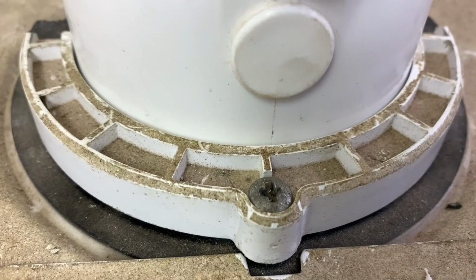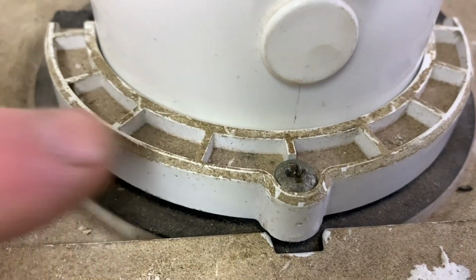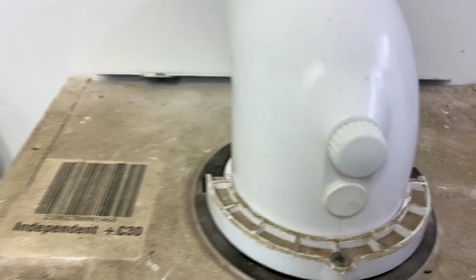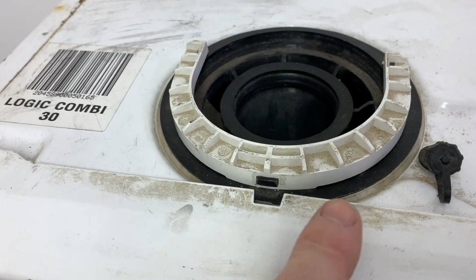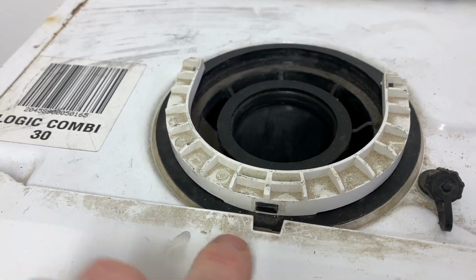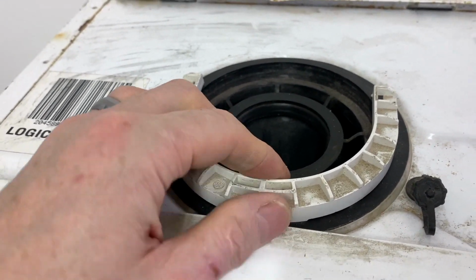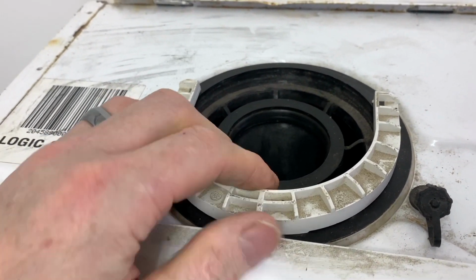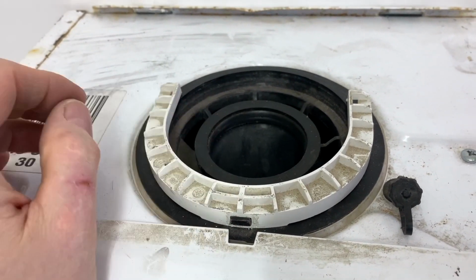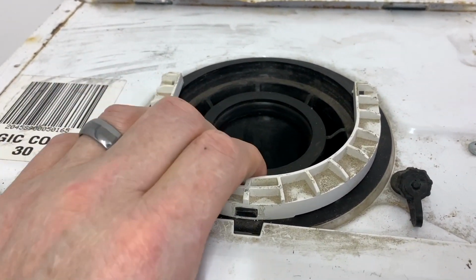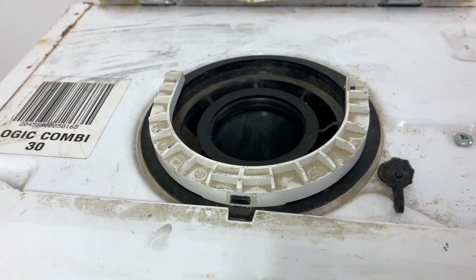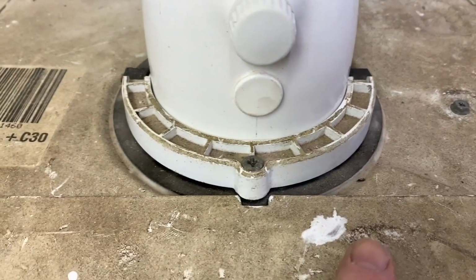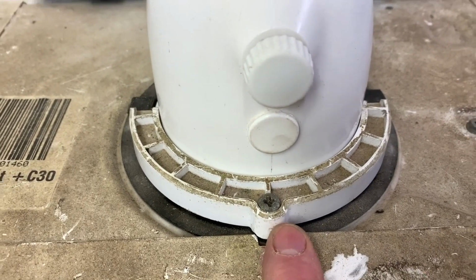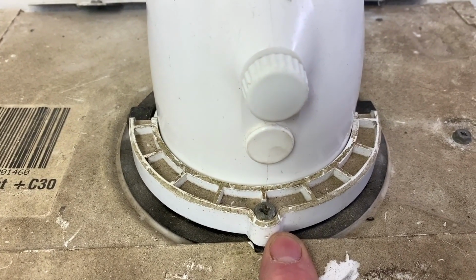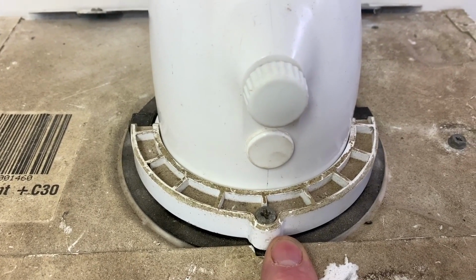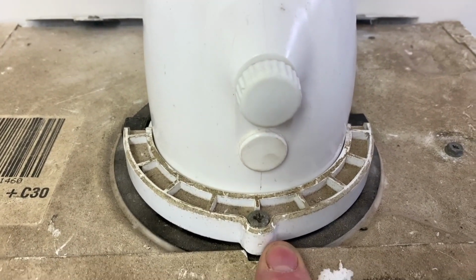First one is the horseshoe clamp that holds the flue on. This one has a screw in it, but if we look at the earlier model, this one doesn't have a screw in it. And what was happening is, if the flue wasn't secure properly, this was pinging off. So if they had a really big fall back to the boiler, this also pinged off. So to counteract that, the manufacturer puts a screw in it. Okay, so this is still in the new range now. About 3 years ago they changed this all again, but we'll try and squeeze that little changes in a bit.